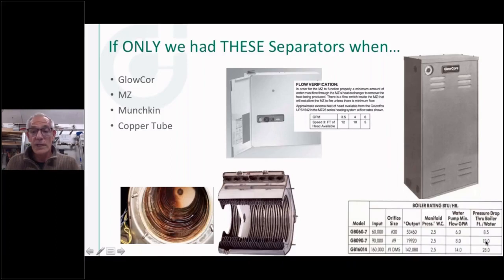And what a lot of us didn't pay attention to, myself included, is that we had to really be sure that when we sized the circulator for this boiler and whatever distribution piping and emitters you're going to tie onto it, you had enough pumping power to cover all that. Rethinking that, if we would have been paying a little bit more attention to primary-secondary piping and hydraulic separators, which is what we're going to talk about tonight, these boilers probably would have done a lot better than they originally did, where people were just trying to treat them like we do a cast iron boiler, which has virtually zero pressure drop going through it.